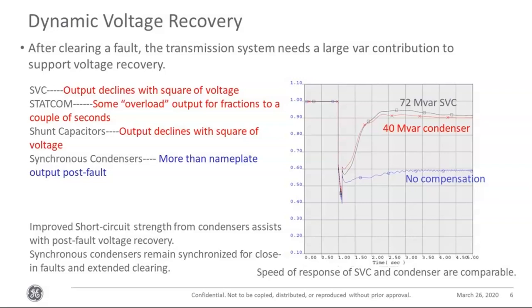response. And even in that, you will see that in the initial portion where you are grappling with that low voltage issue, at that time the condenser gives a faster response. The voltage recovers faster than it does with the higher rated SVC, because the SVC is grappling with the low voltage issues, and then after that, both of them are comparable. With the SVC support, voltage settles at a slightly higher value.